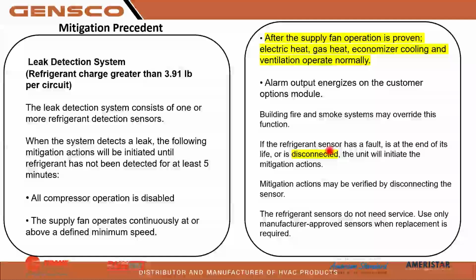If the refrigerant sensor has a fault, is at the end of its life, or is disconnected... Now they do say these things last 10 to 15 years. The unit will initiate the mitigation actions. So again, there's no good way to test these sensors yet. I do believe we are going to get some kind of aerosol can spray where we can spray a small amount of refrigerant in there to actually test it. But as far as testing the sensors, there's no good way to test them yet.